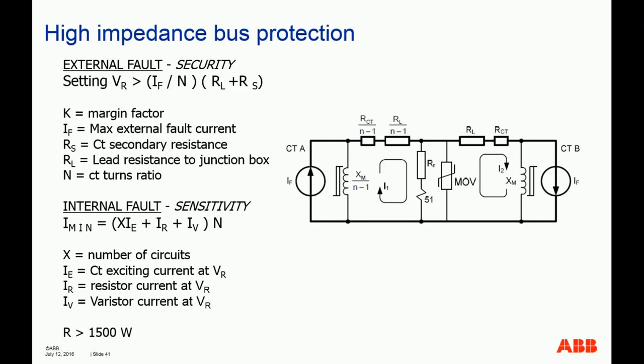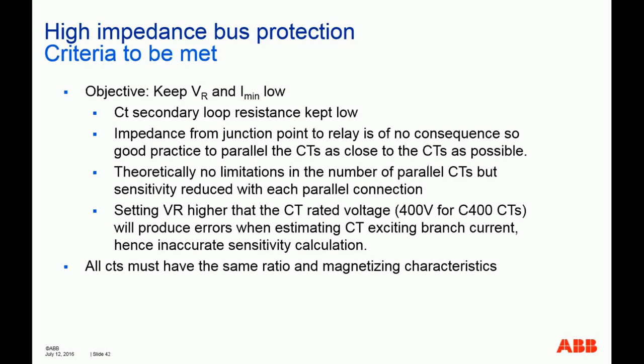So the more CTs you add in parallel, the higher the minimum operating current would be. So in that case, you make it less sensitive. Okay, so that's actually a judgment call. But theoretically, there's no limitation. You can actually keep paralleling your CTs together if you like.